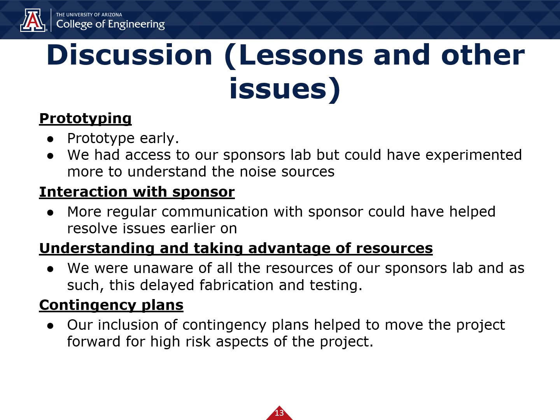After discussing with our sponsor, we were able to find a different amplifier that, while it had a lower gain, would give us the bandwidth needed. We quickly redesigned the electrode PCBs and tested the new active circuit components, which resulted in electrodes that satisfied the bandwidth requirements. From this and other challenges faced, our team learned several valuable lessons in the engineering process.